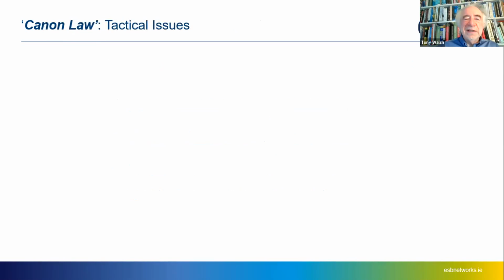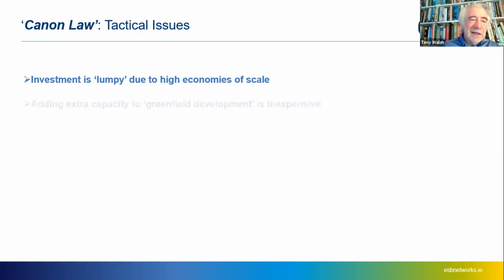Canon law then, if you like, is the tactical issues. The first one is that investment is lumpy due to high economies of scale. I can put in a 400 kVA transformer in a substation, or I can put in a 630 kVA transformer, and the difference in cost might be maybe 15% for the equipment, but the capacity I'm getting is 50% more.